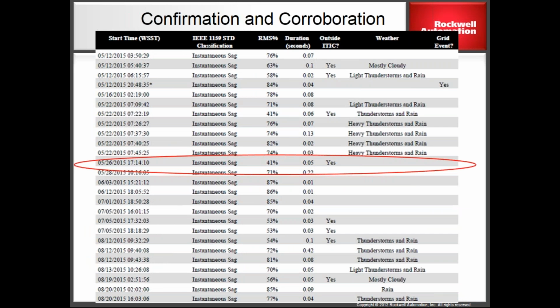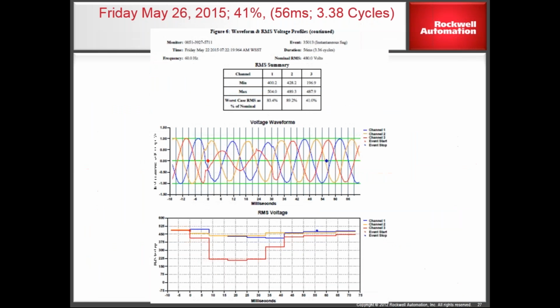Same kind of thing, we can now see what event took place, how low it went, and then this is a 3-cycle graph. This is what would have gone to the owner of that monitor within a minute of the event. You can see by looking at the numbers it went to 41%, but it becomes pretty obvious this is primarily a single-phase event. Anything on that phase went down, and of course 3-phase equipment also went down because one of the phases got creamed. The other 2 single phases weren't too low, probably rode through. So some controls rode through, and most 3-phase stuff went down, and a lot of other controls went down too. That's what would have happened in the factory from this kind of event.